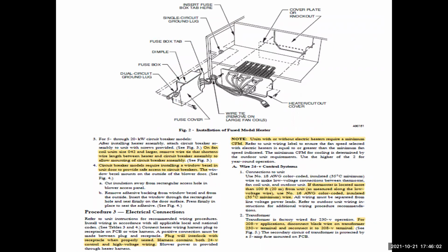Okay. Fan coil units of 3.5 ton or larger, remove the wire tie to lengthen out your wire loom. The wire harness over here is kind of letting you know that it contains high voltage and low voltage. If the thermostat is located more than 100 foot away from the unit, use number 16 gauge color-coded insulated wire. And down here, it's giving you a reminder that your transformer for 208 applications, disconnect the black wire from the 230 and reconnect it to the 208 terminal.